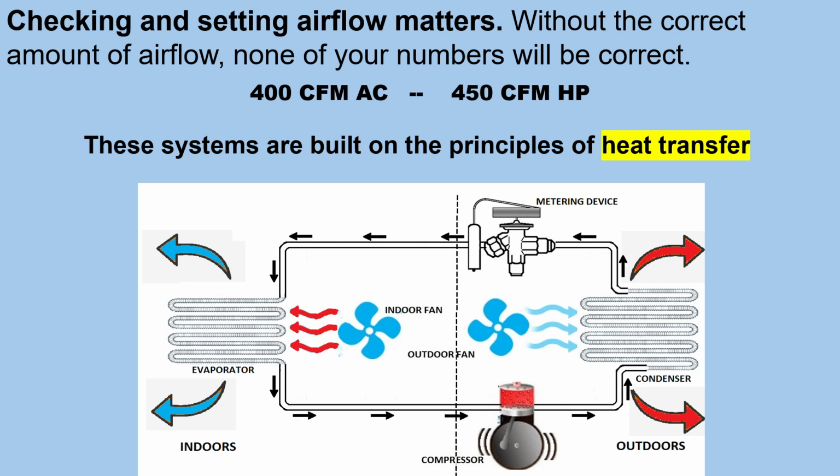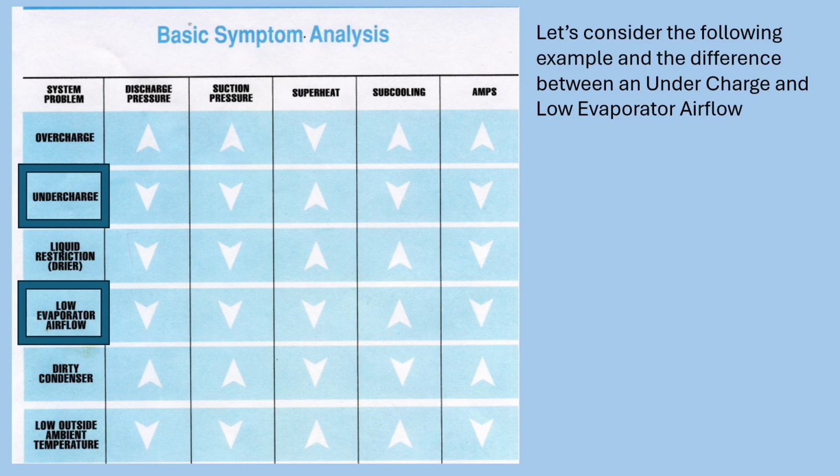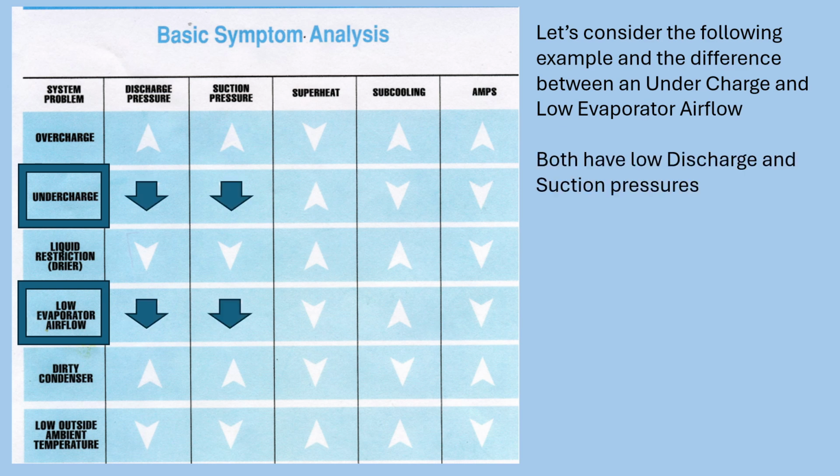These systems are built on the principles of heat transfer. Let's consider the following example and the difference between an undercharge and low evaporator airflow. Both have low discharge and suction pressures. Both have low motor amps.